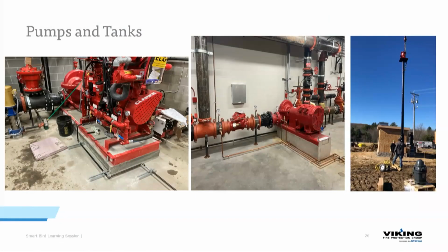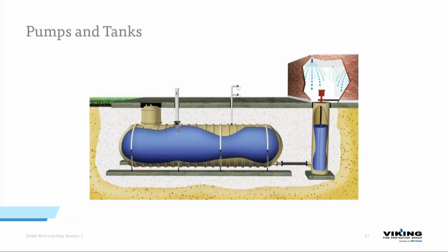On the far right there, you've got a vertical turbine fire pump, and this is the shaft that goes down into the tank or the well. And that's the head right there. That's the power source. So this is a pretty good example. If we look at that vertical turbine fire pump we just looked at, it's going to get lowered down here into this fiberglass well and sits on top of a concrete pad.